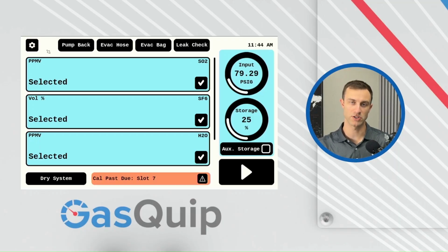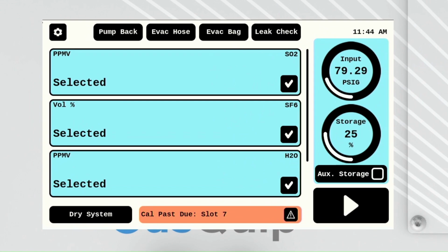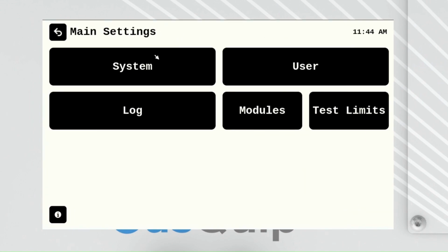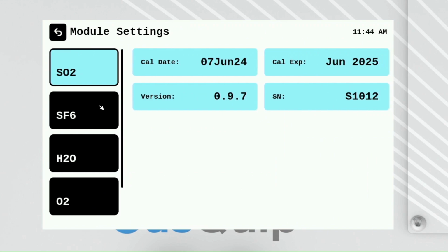To access our module settings and information, we're going to go over to our gear icon here in the top left. We'll go over to modules, and click on the individual module that you would like to get information from. Here we have the original calibration date of the module, the calibration expiration date, the version number, and also the serial number of the individual module. The individual serial number is also printed on the module itself on the side of the black casing. But this calibration expiration date is what tells the system that the module is overdue. It won't lock you out of running a test. It's just there to remind you that it needs to be replaced.